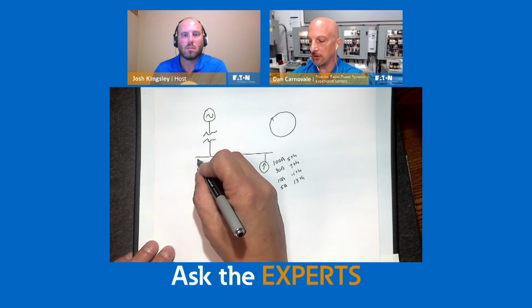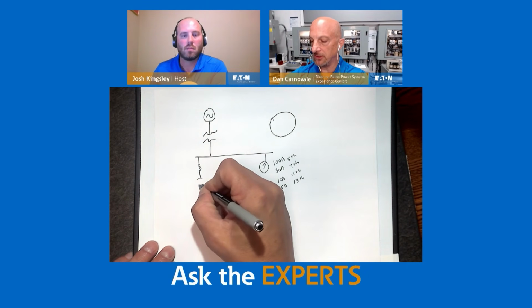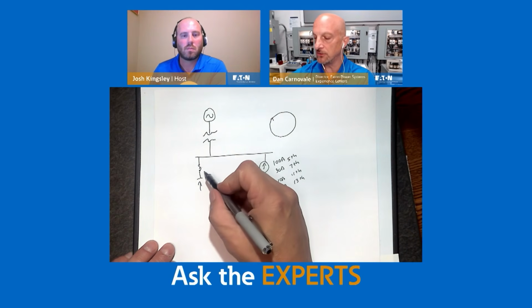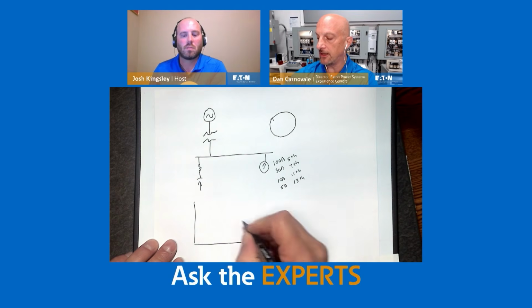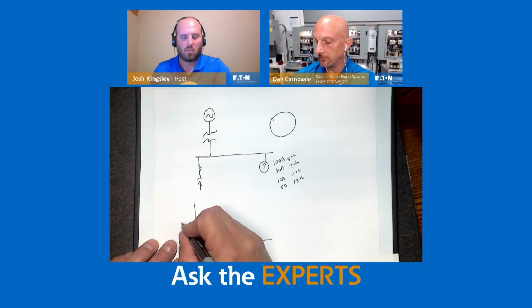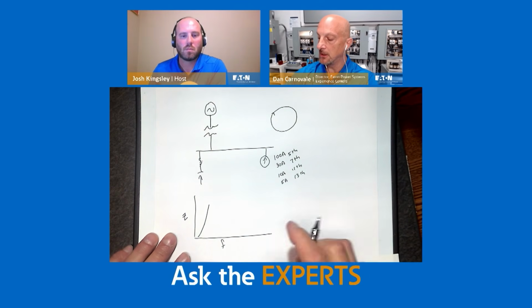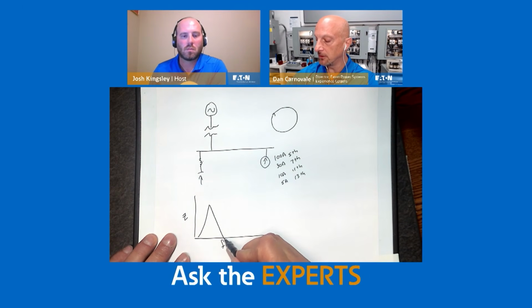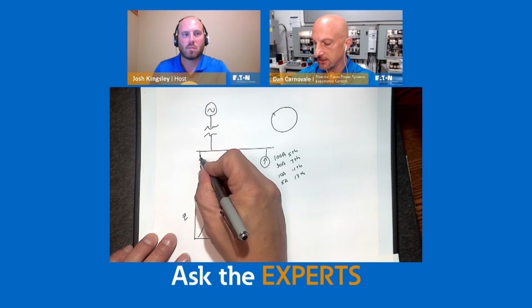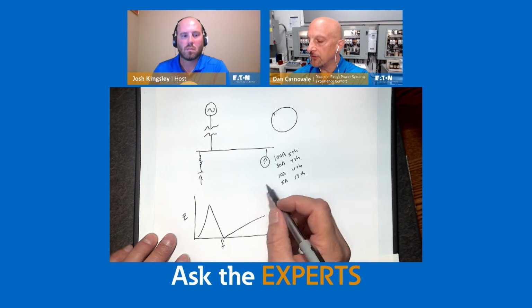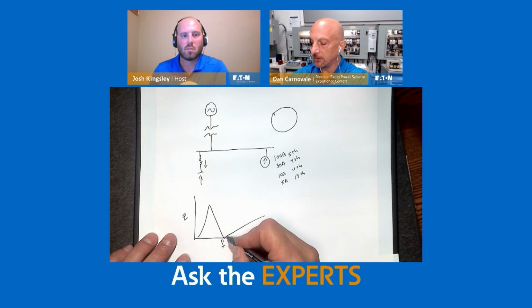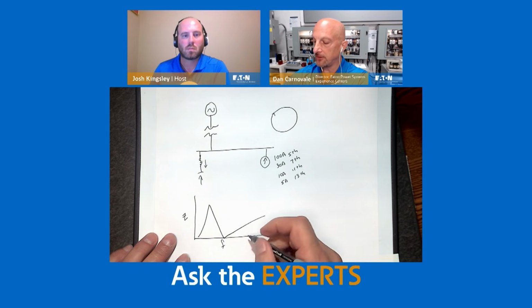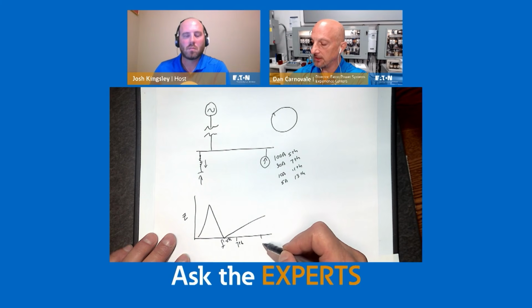If I put a standard harmonic filter in, I mentioned this earlier and kind of glossed over it a little bit, but basically what you do is you tune this filter. And if you look at a frequency spectrum of that, you look at basically something that looks like this. If this is impedance and this is frequency, you have a point where that filter looks very, very close to zero. Now it's not really zero because there's a little bit of resistance in here. So let's address that in terms of losses. If I push current through that path, first of all, only the current that's around this frequency wants to flow through that path, because as you look at the impedance, it's high here and high here. So the fifth harmonic is here, seventh is here, say 11th is here.